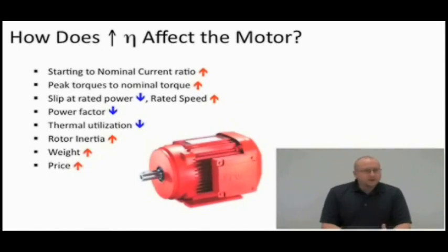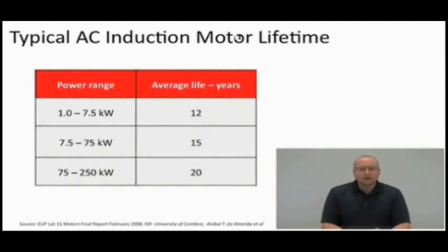Well, one of the things you've got to think about is an asynchronous motor only has 2 moving parts. It's 2 bearings. That's it. They're very solid construction. It's a very simple machine, and they last a long time. They last a very long time. Larger motors can last up to 20 years. So, is it worth it to have an increased efficiency motor in your system? Of course it's worth it, because of the lifetime of the motor.